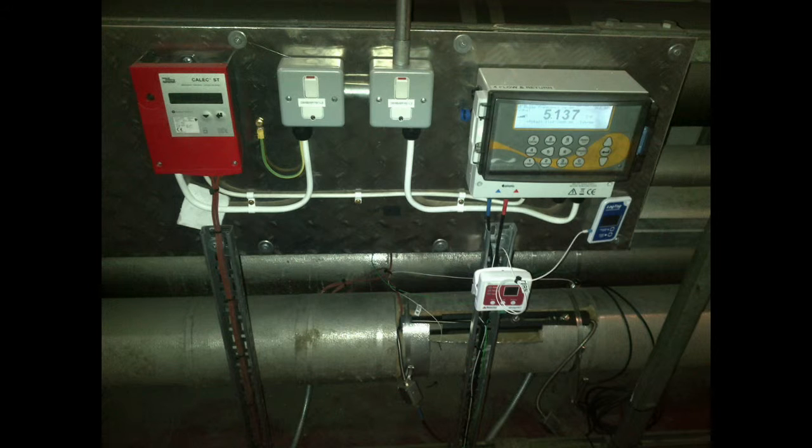Micronics recommended the use of the U1000 and U3000 flow meters with energy calculators and data loggers. They offer a quick and reliable flow measurement solution. They are configured for pipe size, so only nominal configuration on site is required, minimising intervention. The easy-to-follow menu made it a very cost-effective alternative to a traditional inline meter. Furthermore, dry servicing is possible, so that downtime is kept to a minimum, which is especially important for the smooth running of such a busy terminal.